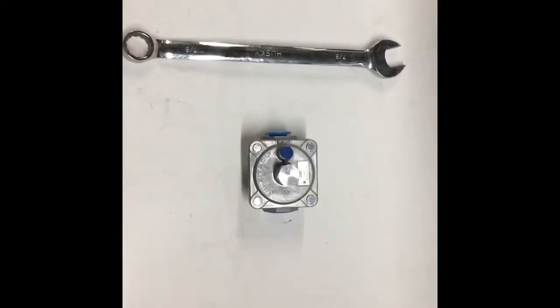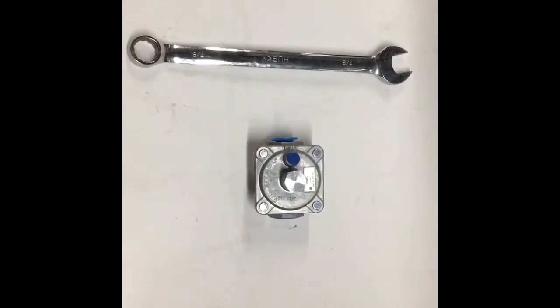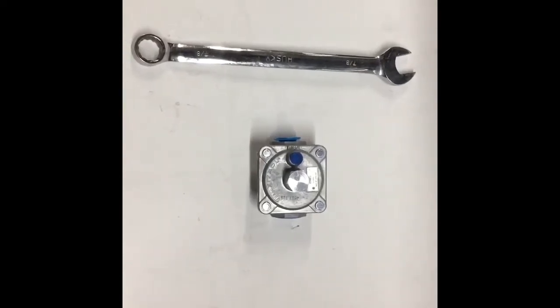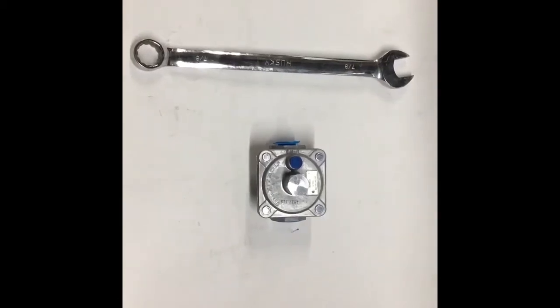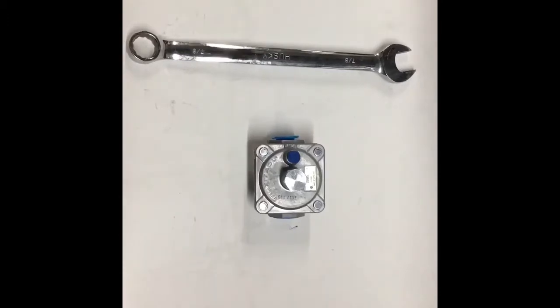In this video we are going to show you how you can convert an appliance regulator from natural gas to propane. These regulators come set from the manufacturer for natural gas, so if you are needing to convert to propane you will need to convert the appliance regulator.